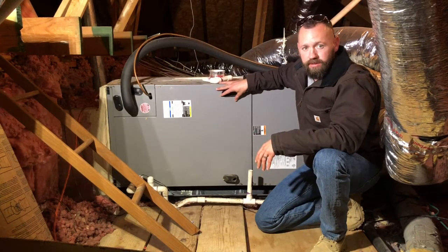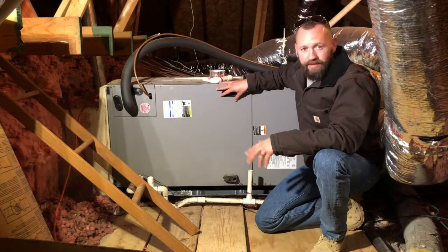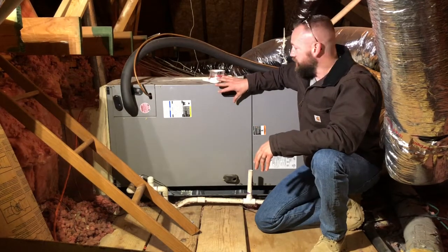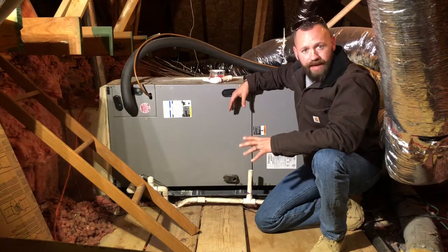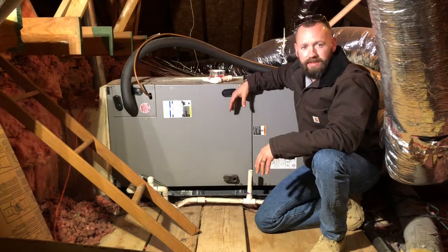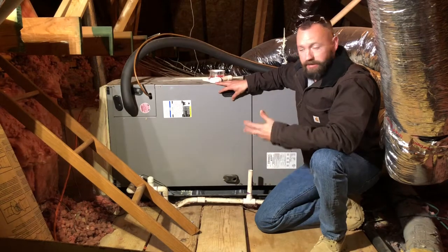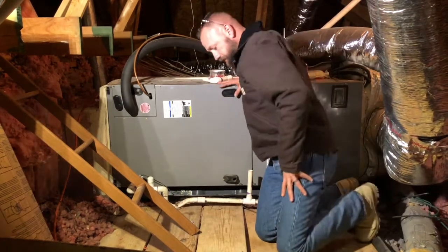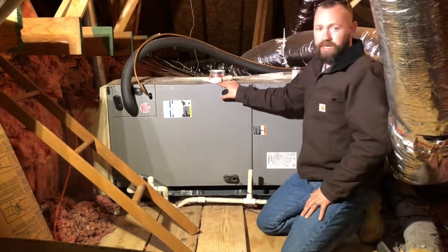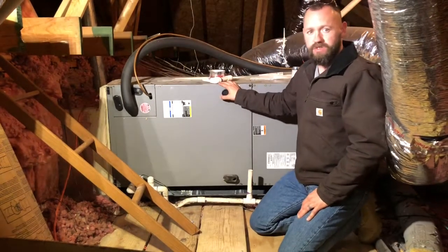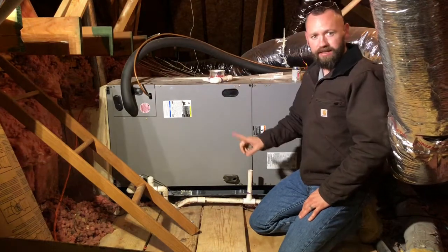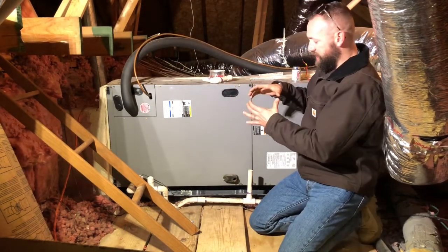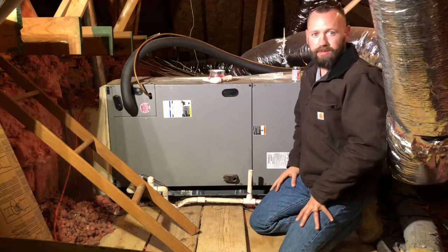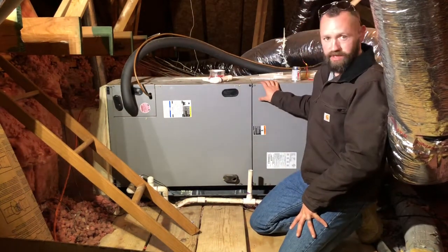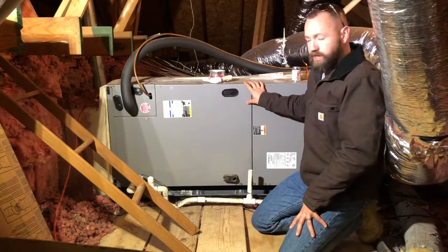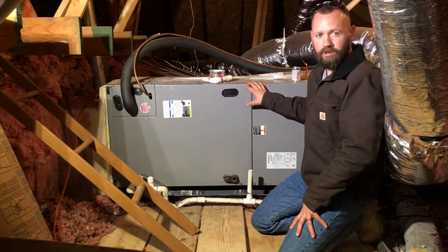Now the indoor unit has two names. If you have gas and it's a gas furnace, the indoor unit would be a furnace. If you don't have gas, if it's electric or a heat pump, then the indoor unit is called an air handler. Now this that we've got behind us, this is an air handler. And a quick, easy way to tell is a gas furnace is going to have one, a gas line coming into the unit, and two, a big metal pipe venting out the products of combustion. This has neither of those. This is just an air handler. So this is going to be either a heat pump or electric heat.